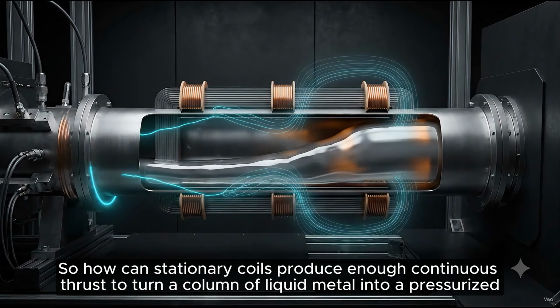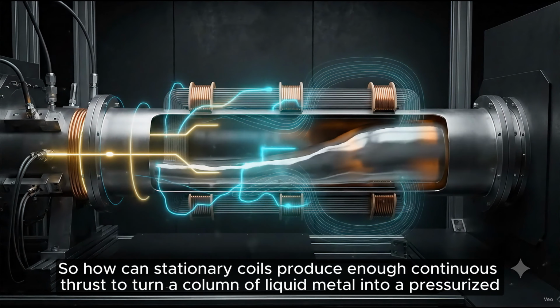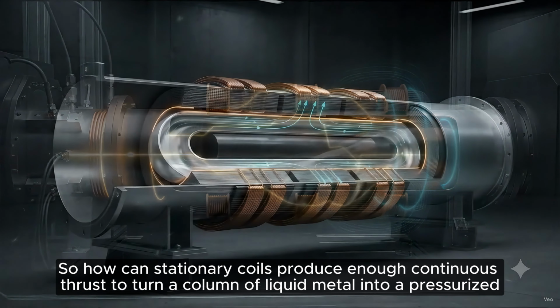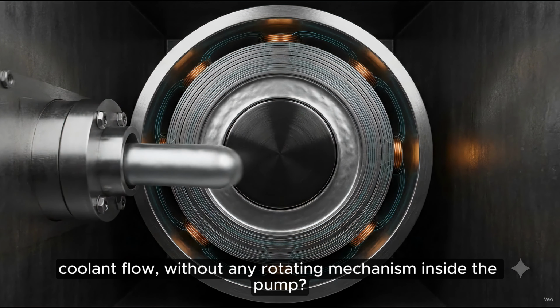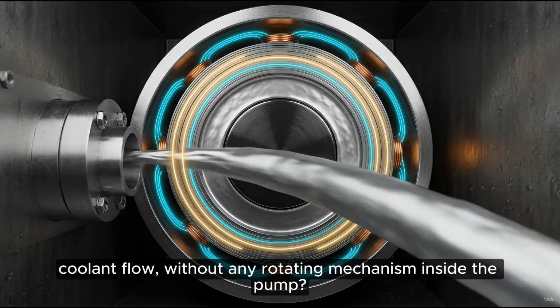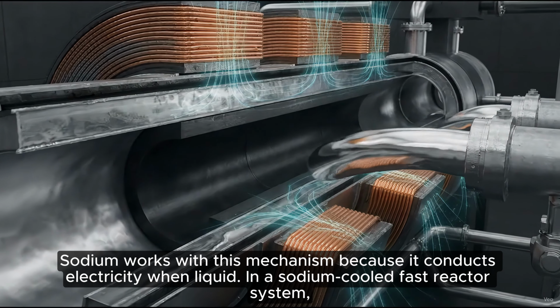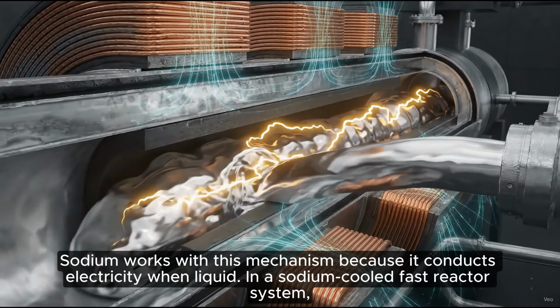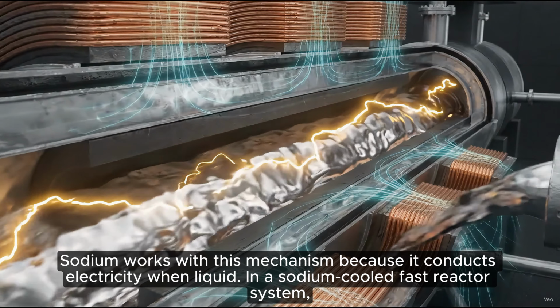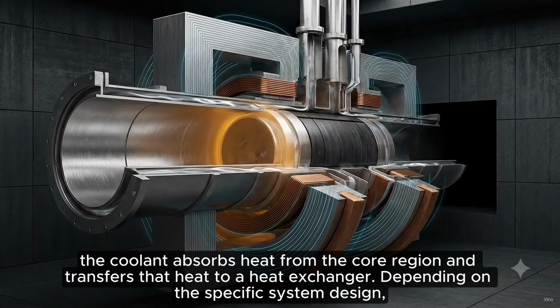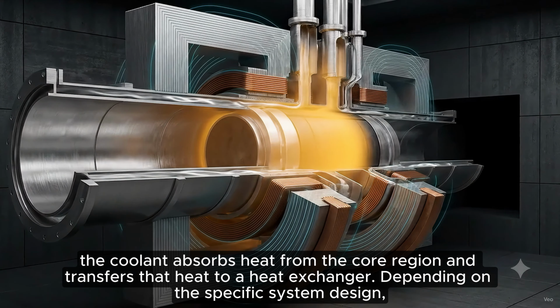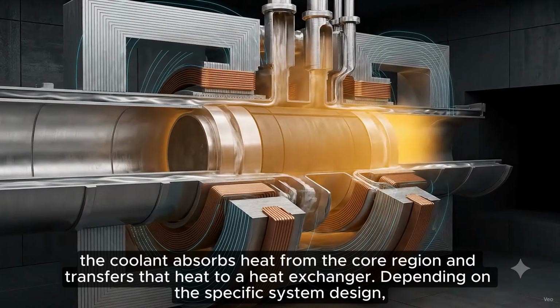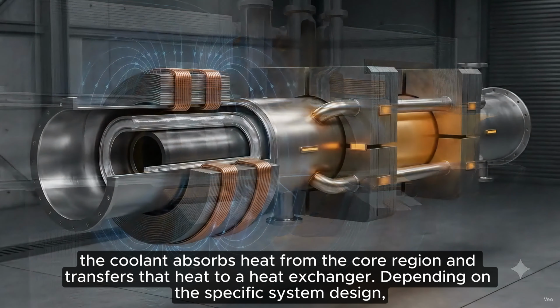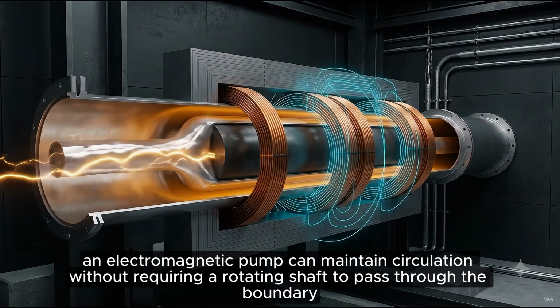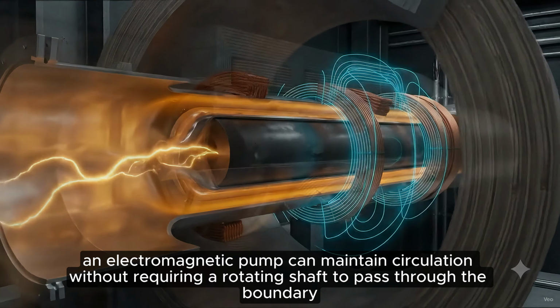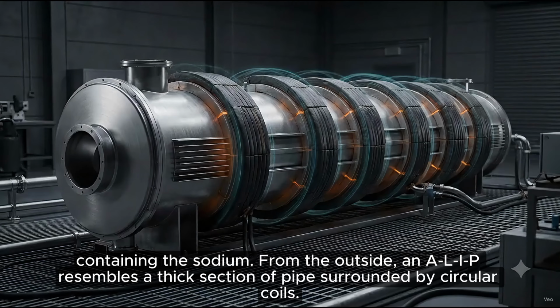So how can stationary coils produce enough continuous thrust to turn a column of liquid metal into a pressurized coolant flow without any rotating mechanism inside the pump? Sodium works with this mechanism because it conducts electricity when liquid. In a sodium-cooled fast reactor system, the coolant absorbs heat from the core region and transfers that heat to a heat exchanger. Depending on the specific system design, an electromagnetic pump can maintain circulation without requiring a rotating shaft to pass through the boundary containing the sodium.